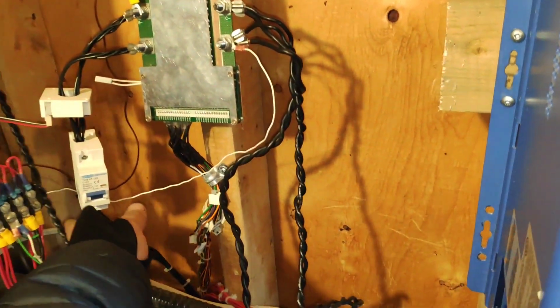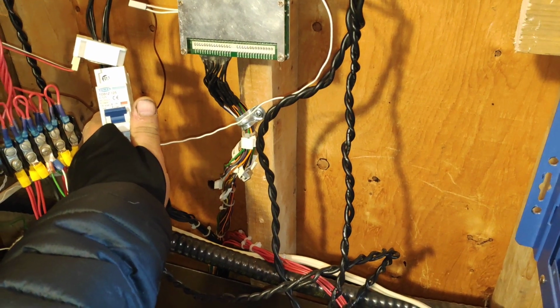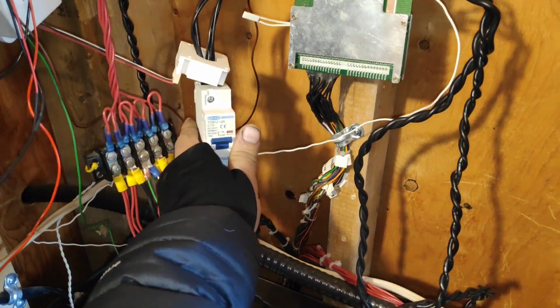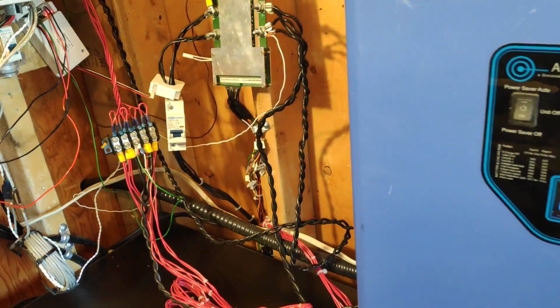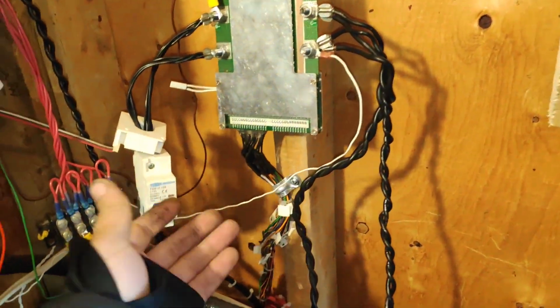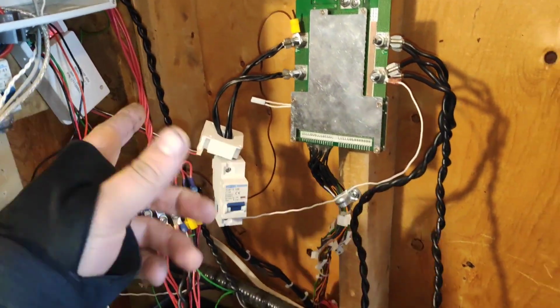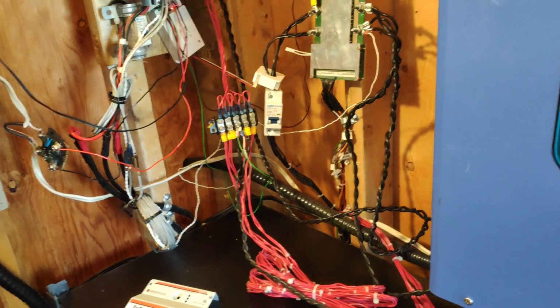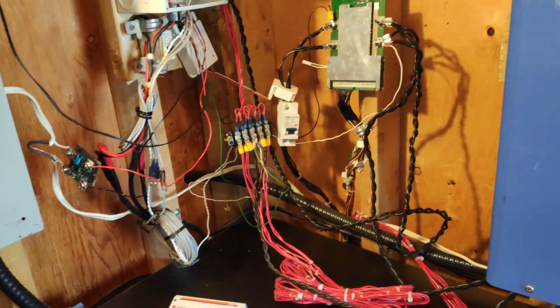For the breaker, I have this C125 breaker here, which I believe is rated for up to 125 amps of current. Usually the last 2 numbers are the current rating from what I recall. Works fine, though I would never run it that hard.